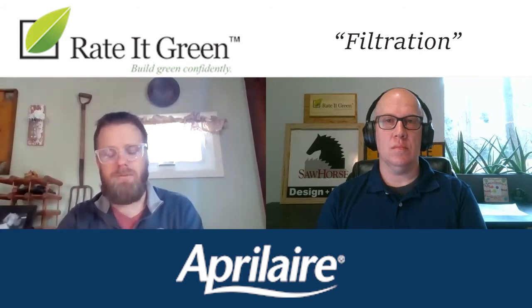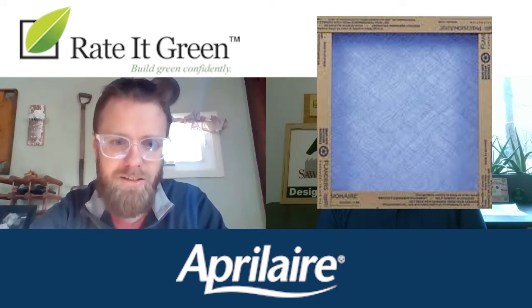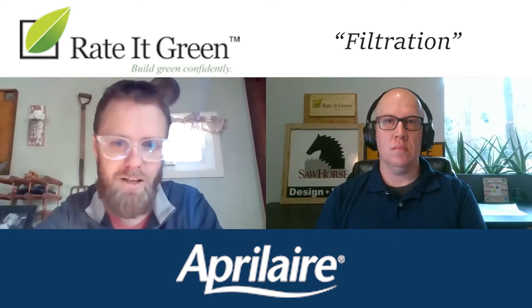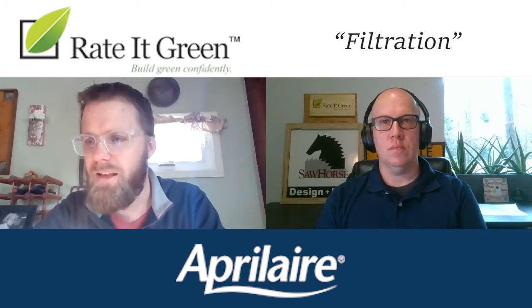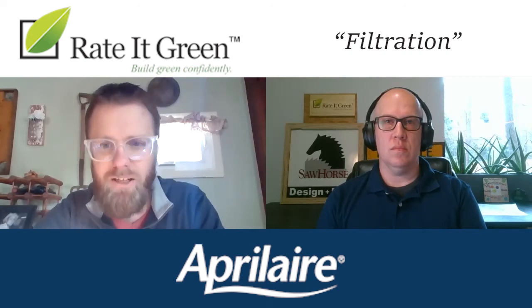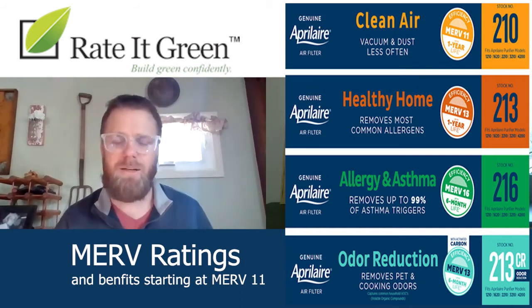Where it gets a little more complicated for the consumer is: what exact type of filter do they need? If you're going down in your basement and you've got a one-inch filter — one of those blue mesh ones that you could hold up and see through — that's really there to protect your HVAC system, so that things don't go in and clog your blower motor. As far as human health is concerned, that's just not what they're designed for. You can start your high-efficiency filtration at MERV 11. That's where you're going to start getting mold spores and some of the particles released in the air from using hairspray, having pets in the house, and some types of bacteria.